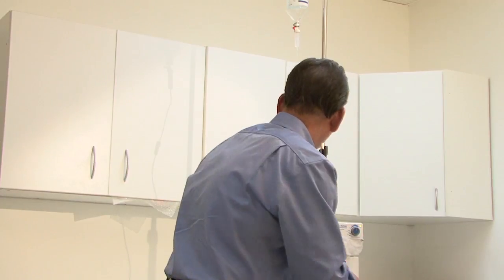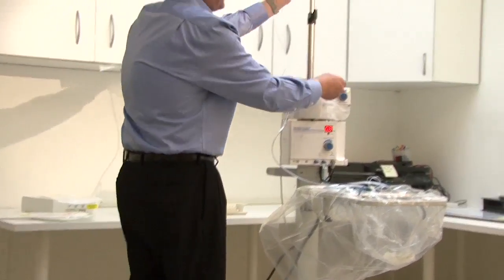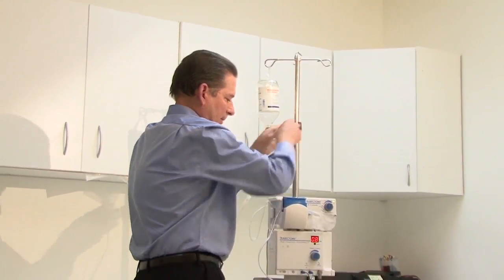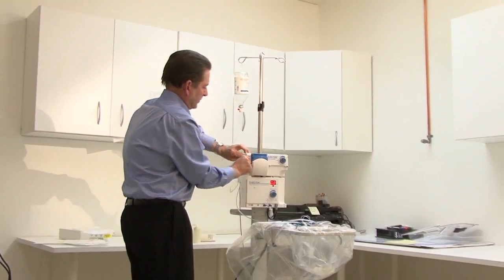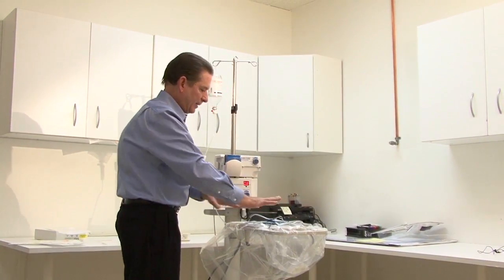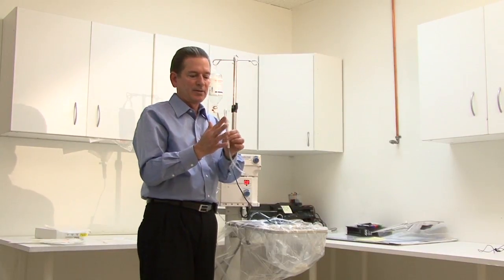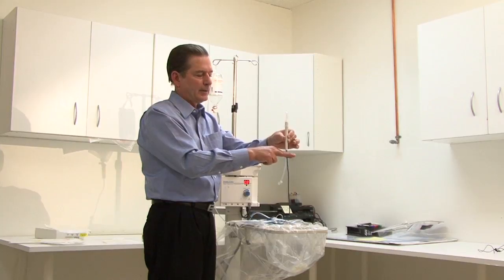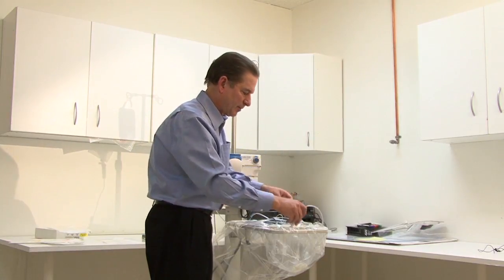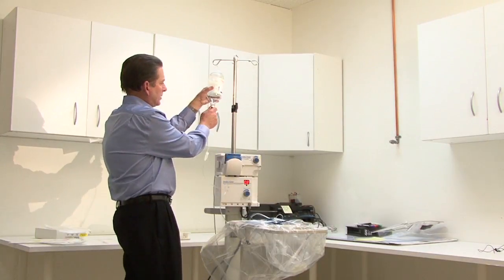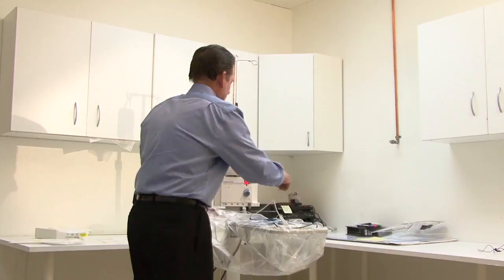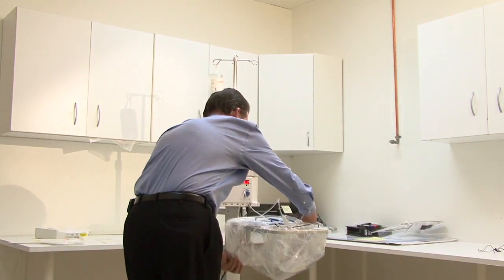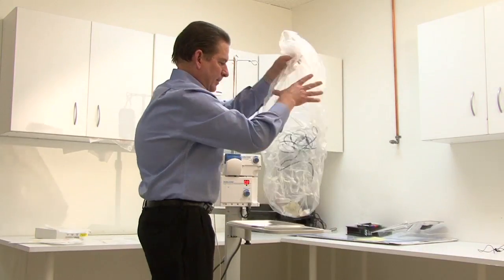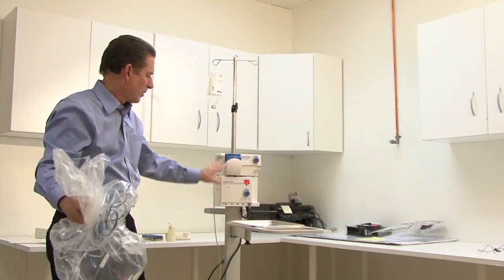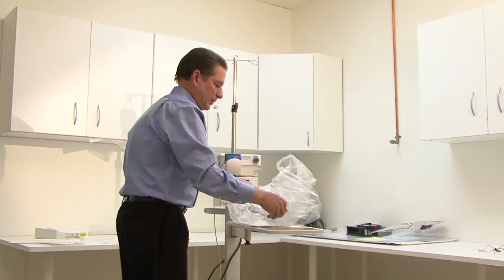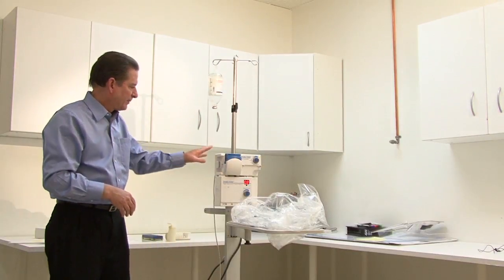And cleanup of the trabectome is very simple because everything's disposable. Basically, it's just the reverse of setting things up. We can just go ahead and remove the items from the pump. The handpiece, everything's single use. Most hospitals will consider this a sharp, so the easiest way to dispose of it is to just cut off the cord, take the whole handpiece, and toss it into your sharps disposal. However you, at your facility, dispose of bottle spikes as appropriate, and then you basically can just remove everything, and we're all cleaned up and ready for the next patient. So it's a very simple system to break down and to be ready for the next surgery.